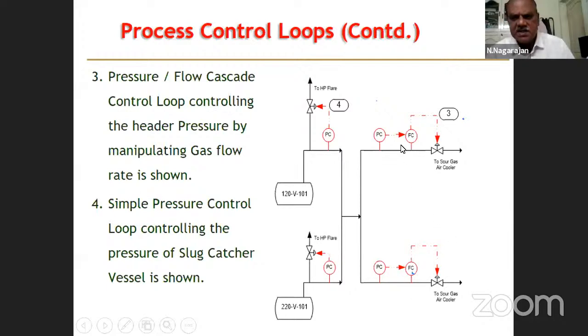Okay, it's a pressure control. This is a cascade control. You can see it's a cascade control. Pressure signal and flow signal both are measured and they are compared. The control action goes from the flow control to the control valve. So this is a cascade control of pressure and flow. This is a simple pressure control. This is a feedback control. You measure the pressure signal and then allow the excess pressure to the flare.